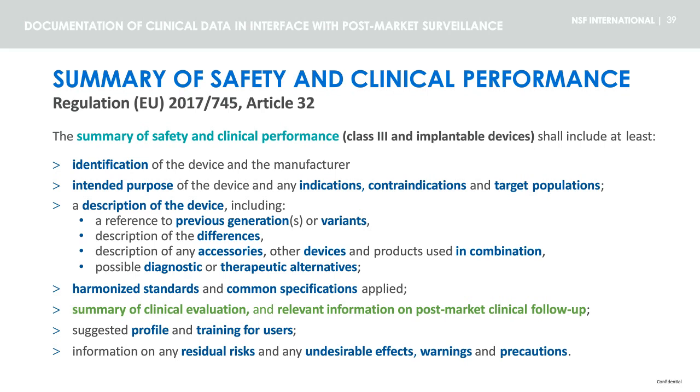It should also include harmonized standards and common specifications applied, information on profile and training for users, residual risks, undesirable effects, warnings and precautions, and importantly, also a summary of the clinical evaluation and relevant information on post-market clinical follow-up. The summary of safety and clinical performance shall be made available via EUDAMED and should be updated annually.